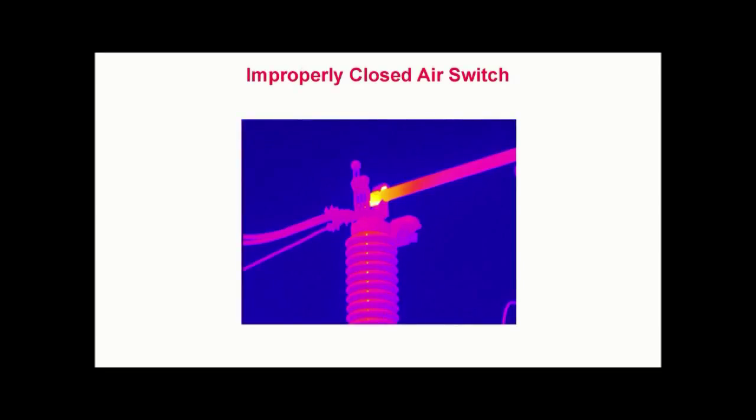Improperly closed air switch. In this thermogram from an outdoor substation, we see localized heating within the jaw of a large air switch. In this image, excess heat is shown in yellow and white. Upon further investigation, it was found that the switch was not properly closed.